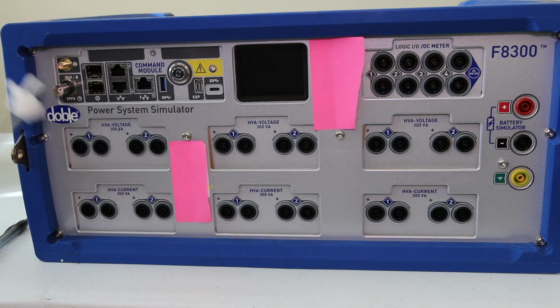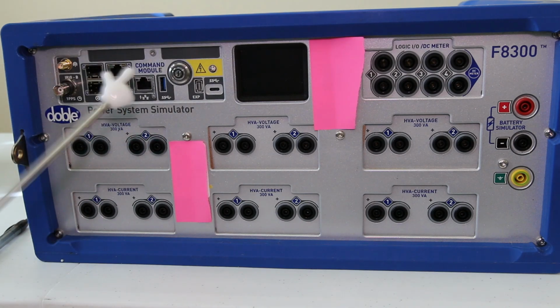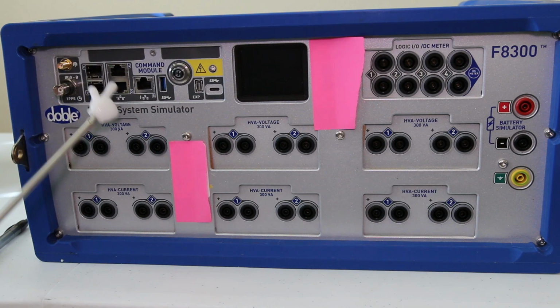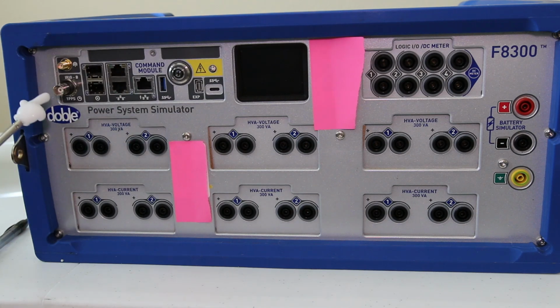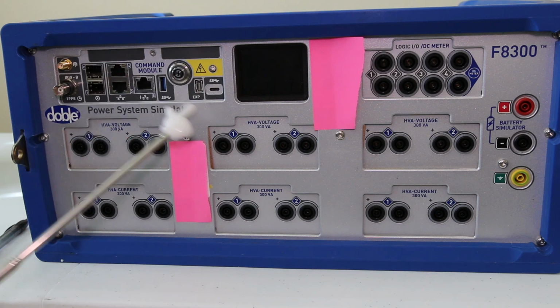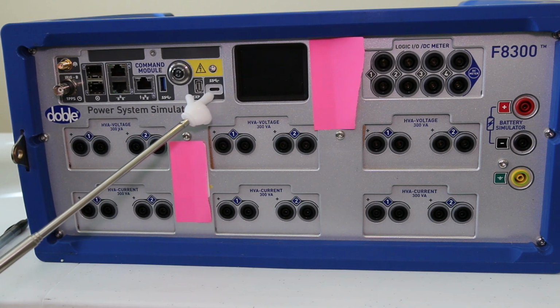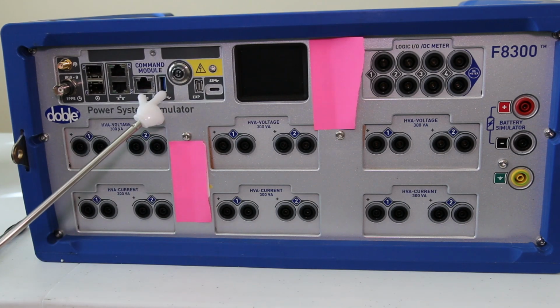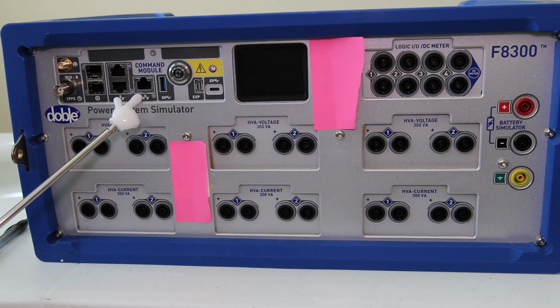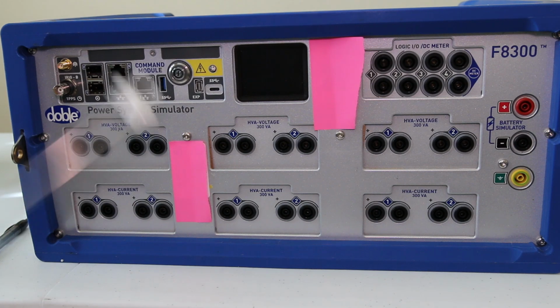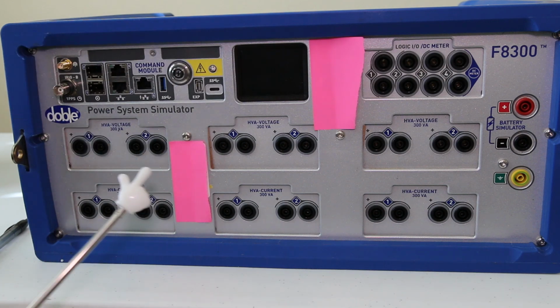The reason this upgrade was really brought about is specifically for use in digital substations. IEC 61850 equipment just requires a lot more connection than older relays do. So we've got a GPS antenna—you can directly connect a GPS antenna, IRIG-B input for time sync in your substation. We've got a couple convertible fiber ports, obviously your old LAN connections, regular USB, and we do have a USB-C, which is nice. This is USB 3.0, and then your standard regular USB-A 3.0 port, as well as, I think, gigabit Ethernet, which is really, really nice. So we have a lot more options, a lot more connectivity on the top of this.